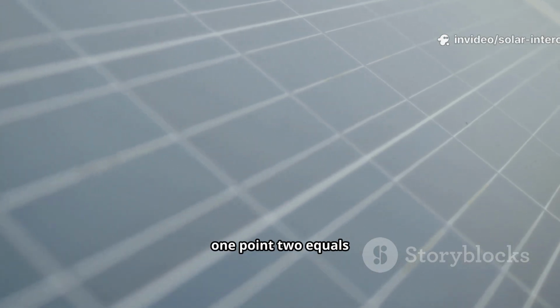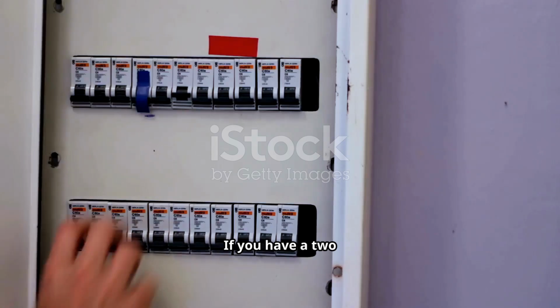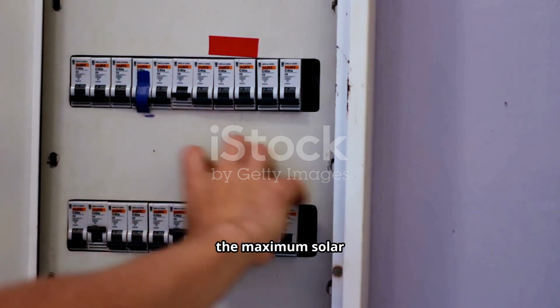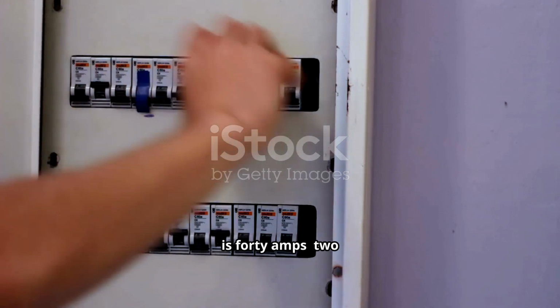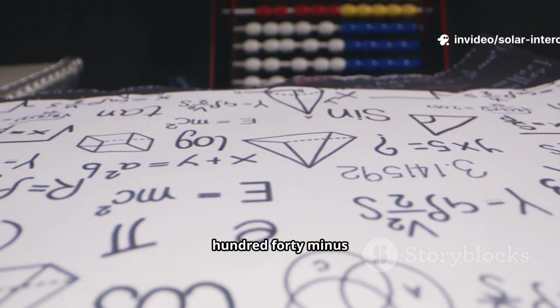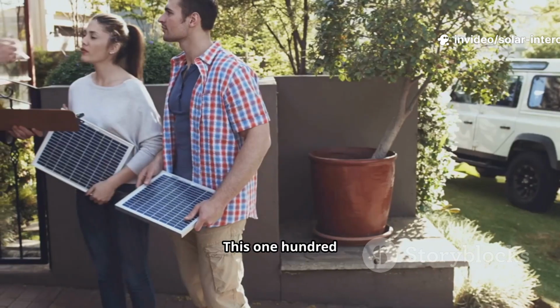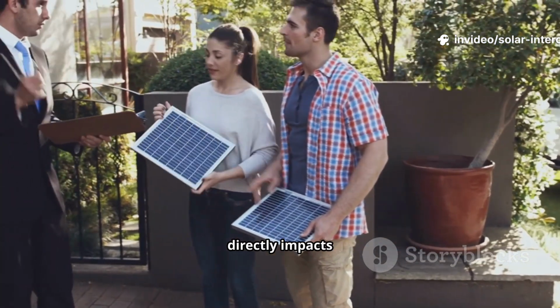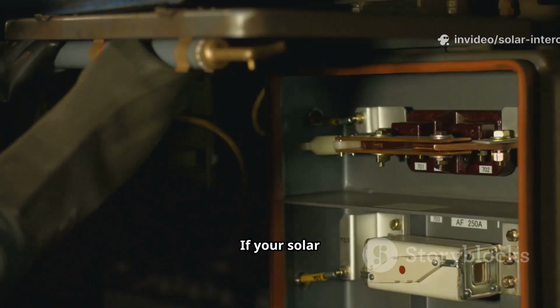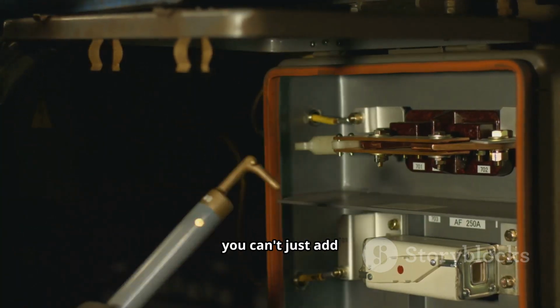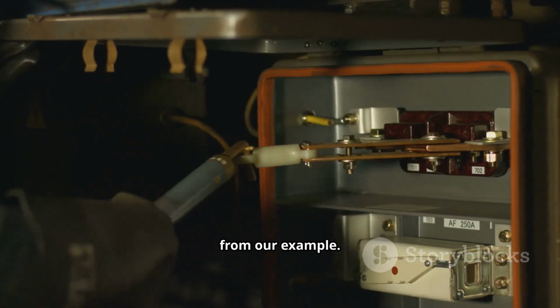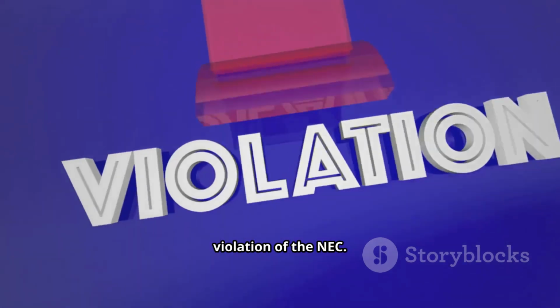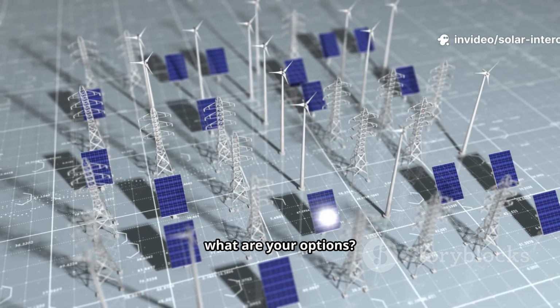200 times 1.2 equals 240. If you have a 200-amp main breaker, the maximum solar breaker you can add is 40 amps. 240 minus 200 equals 40. This 120% rule directly impacts your solar system design. If your solar system needs a 60-amp breaker, you can't just add it to the 200-amp panel from our example. You'd be in violation of the NEC. So what are your options?